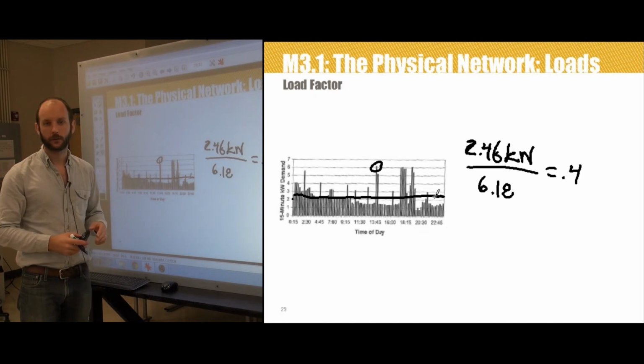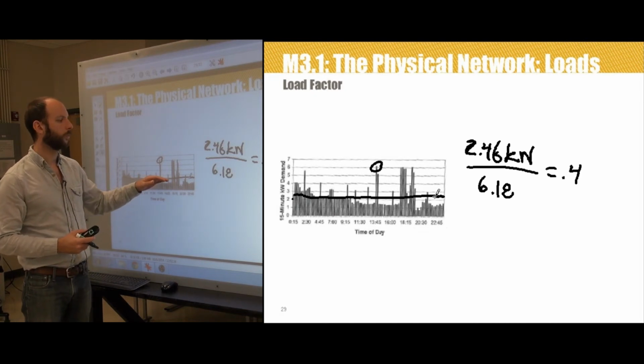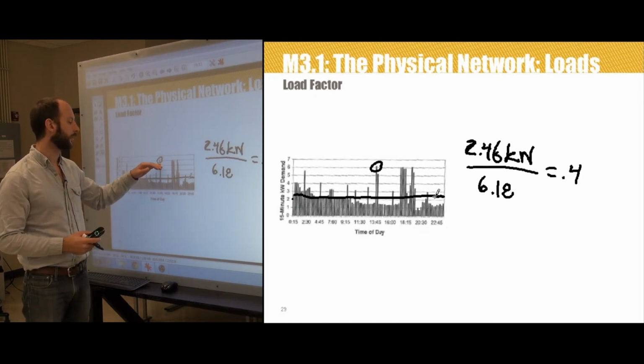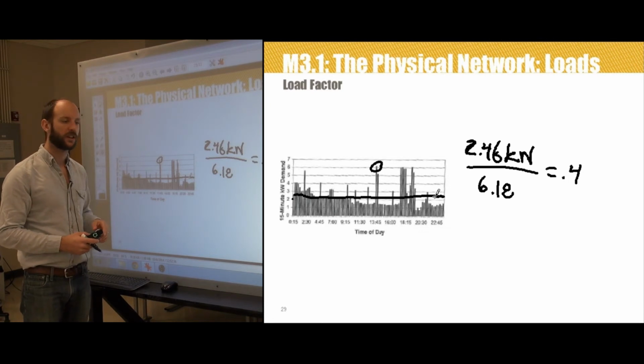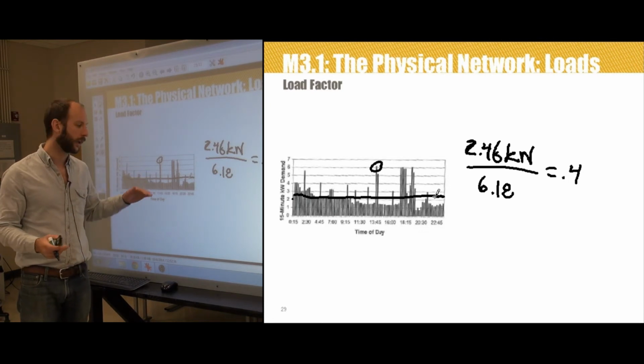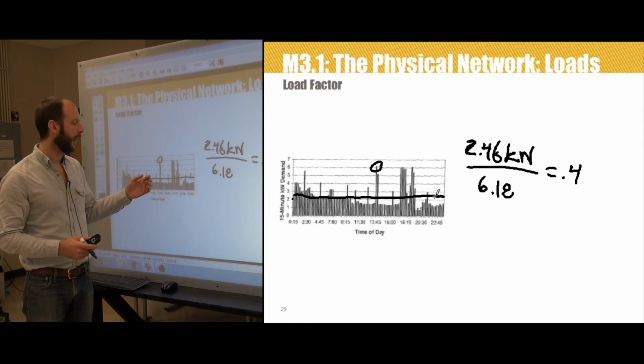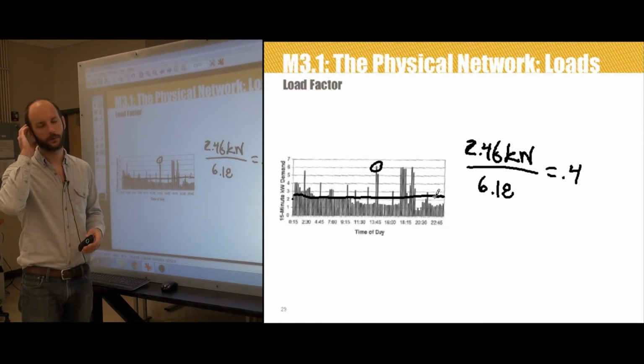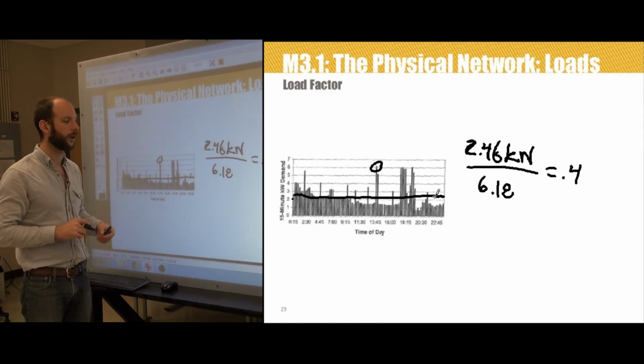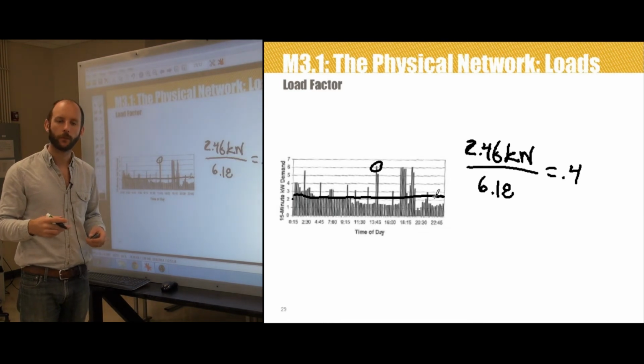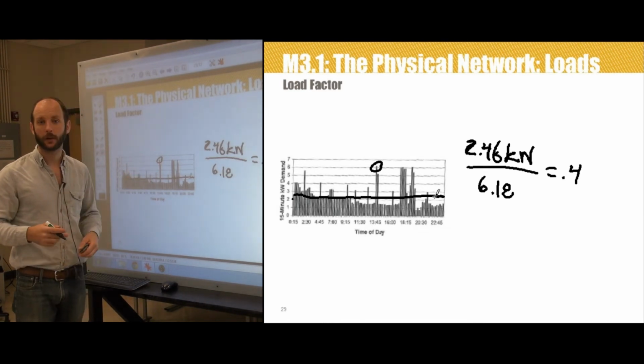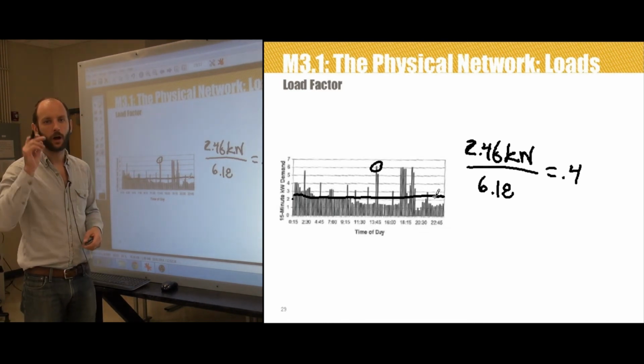High load factors are actually, while one would be ideal from a utilization aspect, doesn't give you any room for growth, right? So you can't ask for any more energy to be delivered to customers or power to be delivered to customers if you've got a load factor of 1. So they typically don't want to operate at a load factor of about 1.